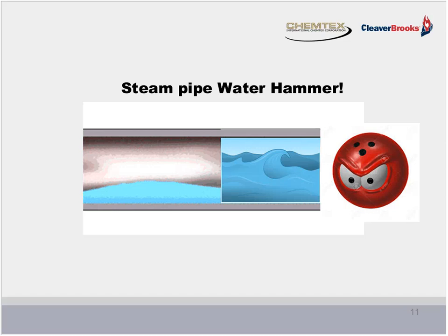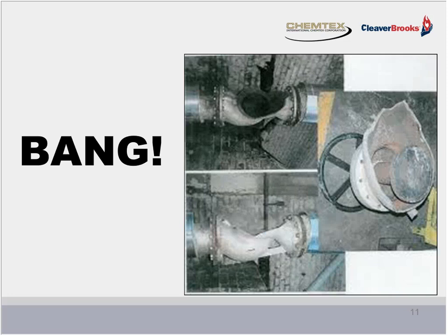it hits a 45 or 90 degree angle or a weakened section, bang, the section of pipe literally explodes, and much of that saturated liquid flashes to steam and expands 1,600 times, causing serious injury or death to those unfortunates in its destructive path. And that's to say nothing about the property damage that's incurred. So water hammer is extremely dangerous.